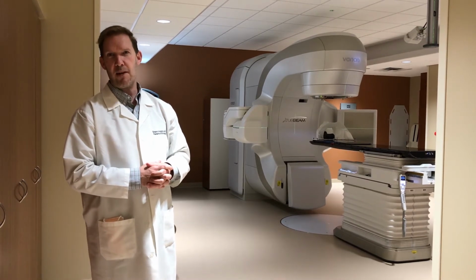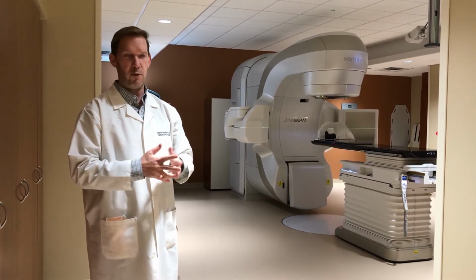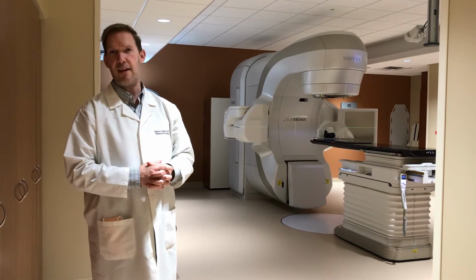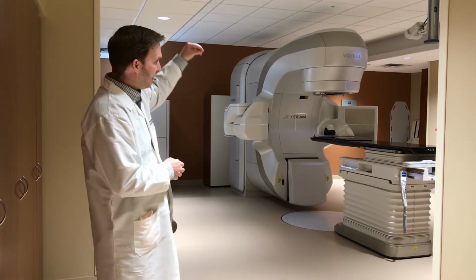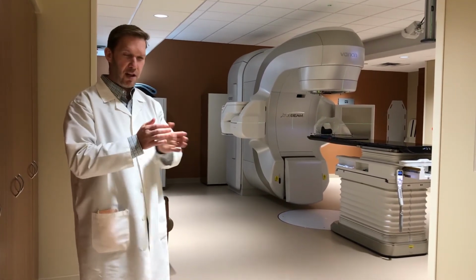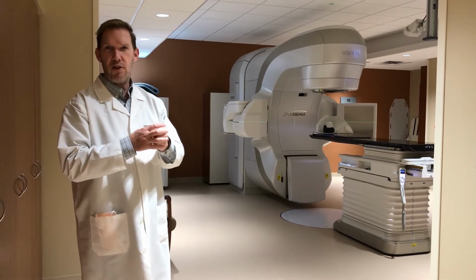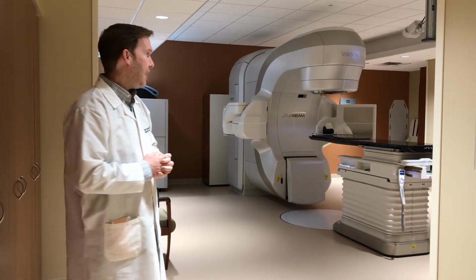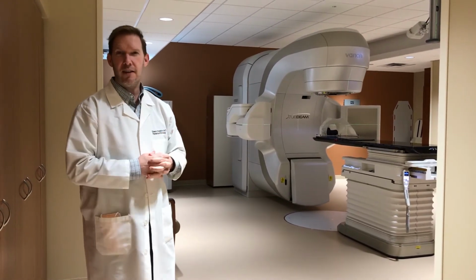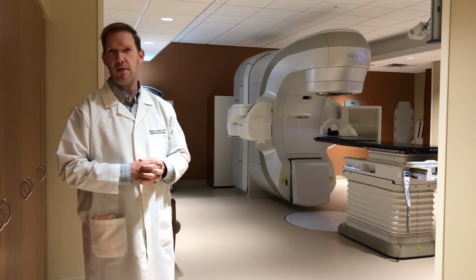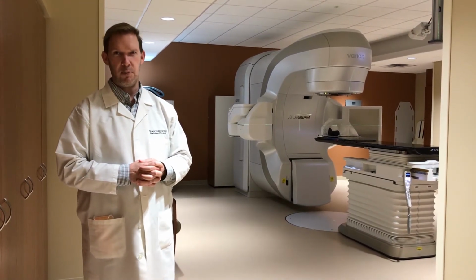And it's about 1,000 times more powerful than what they would use for a CT scan or for a chest X-ray. So as that is directed down toward the patient, we can shape the beam with the aperture, the opening in the head of the machine, and the table can tilt and accommodate a patient to make sure that they're in the correct position so we can make it extremely precise.